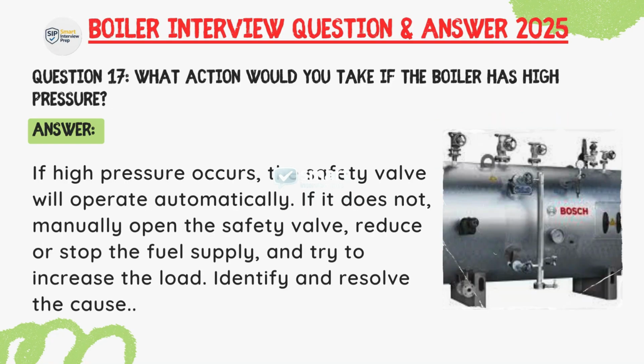Question: What action would you take if the boiler has a low water level? Answer: Low water level is an emergency. Immediately stop the fuel supply. Start the feedwater pump if safe, and allow the boiler to cool down. Identify and resolve the cause.